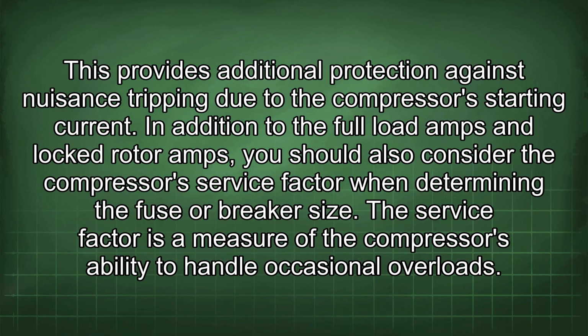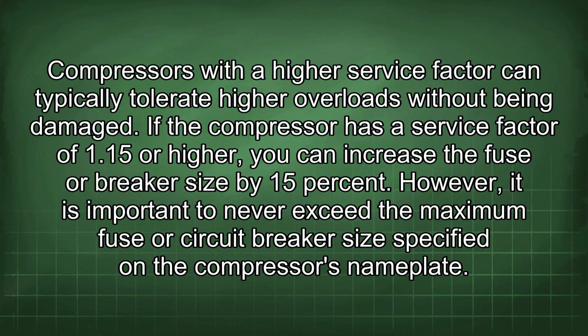In addition to the full load amps and locked rotor amps, you should also consider the compressor's service factor when determining the fuse or breaker size. The service factor is a measure of the compressor's ability to handle occasional overloads. Compressors with a higher service factor can typically tolerate higher overloads without being damaged. If the compressor has a service factor of 1.15 or higher, you can increase the fuse or breaker size by 15%. However, it is important to never exceed the maximum fuse or circuit breaker size specified on the compressor's nameplate.